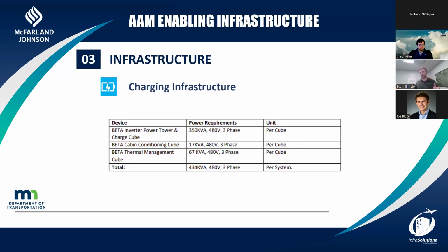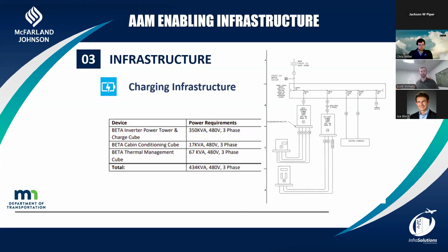These are some numbers I feel will be useful to the engineers doing planning. You have your beta inverter power tower and charge cube, which draws 350 kVA, beta cabin conditioning at 17 kVA, and beta thermal management cube at 67 kVA. The beta inverter tower and charge cube doesn't have a continuous load factor applied to it, so keep that in mind. That would fall under your NFPA 70, so you need to multiply that by 1.25 if you're planning for that future load. Just wanted to show you some raw numbers. So you're sitting around 434 kVA with no safety factor, and you'll be over 500 once you apply that safety factor. So you can figure out what size transformers you're going to need.